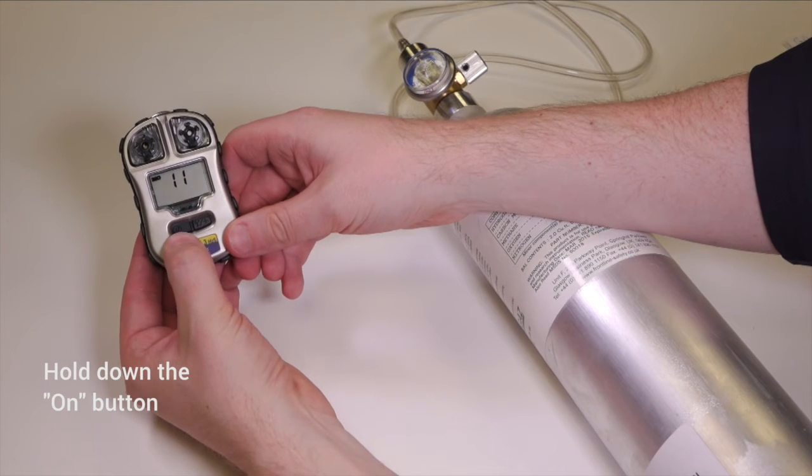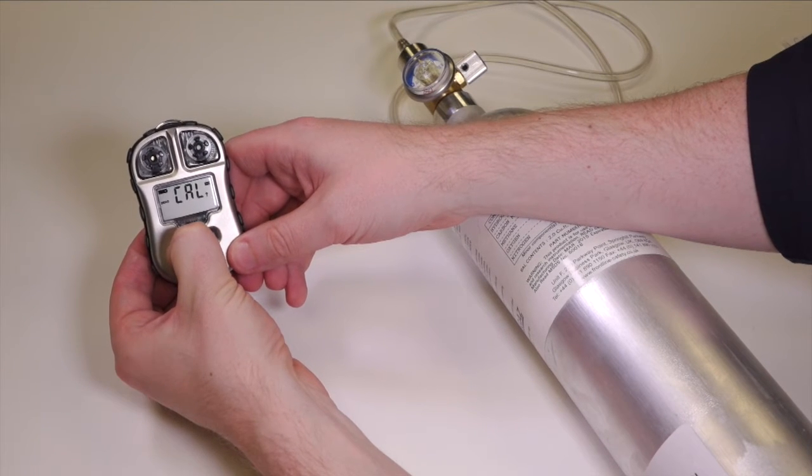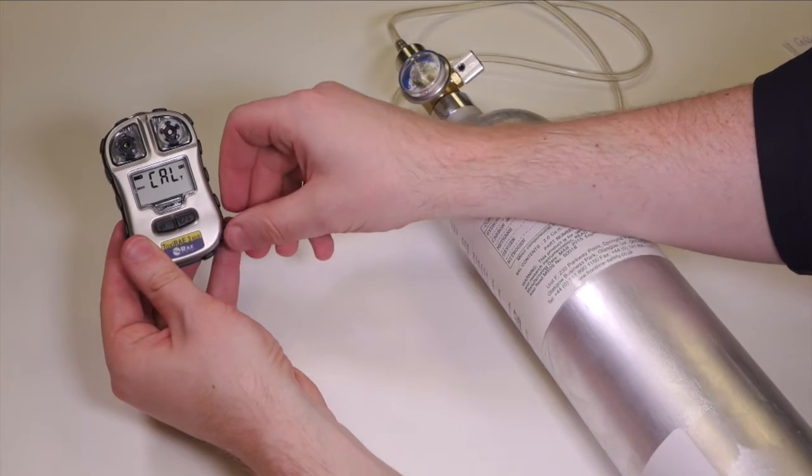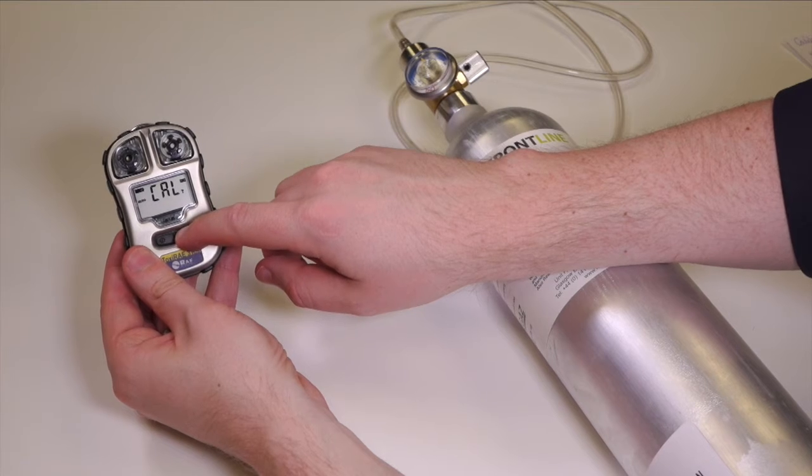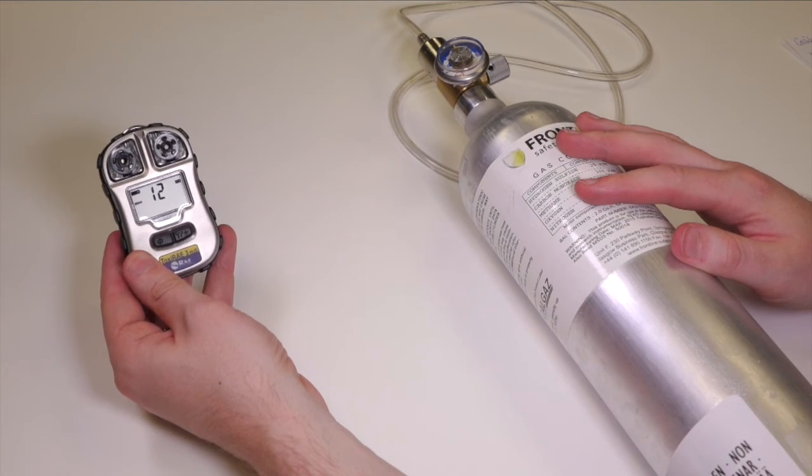Hold down what is the on key or the left hand key and that's now asking us if we want to perform a zero cal. So we'll say yes to that. That's going to zero the sensors, make sure you're in fresh air before you do that and that takes 15 seconds as you can see.